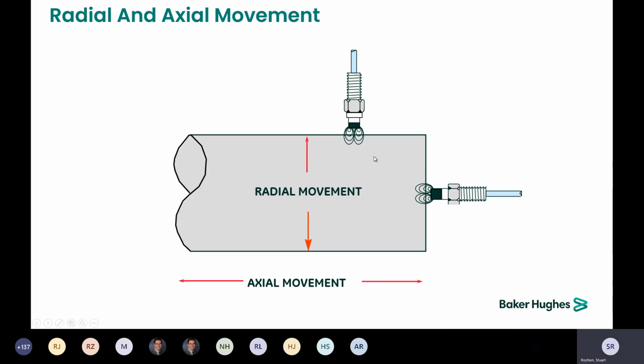We do both radial and axial measurements with proximity probes. Quite often everybody's familiar with the XY vibration component of using prox probes on a fluid film bearing. One thing that many people don't pay a lot of attention to is that the DC component can also be used to measure the position of the shaft in the clearance of the bearing.